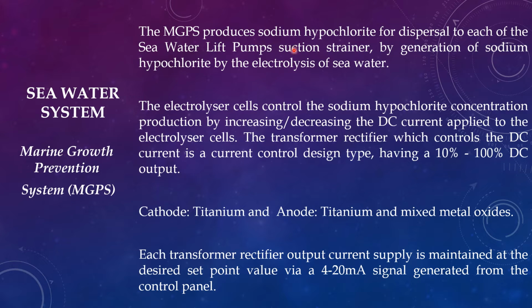The MGPS produces sodium hypochlorite for dispersal to each of the seawater lift pump suction strainers by generation of sodium hypochlorite by the electrolysis of seawater. The electrolyzer cells control the sodium hypochlorite concentration by increasing or decreasing the direct current applied to the electrolyzer cell. The transformer rectifier, which controls the direct current, is a current control design type having 10% to 100% direct current output, which is used in the electrolyzer cell to produce sodium hypochlorite. Titanium is used as the cathode, and titanium with mixed metal oxide is used as the anode in the electrolyzer cells.